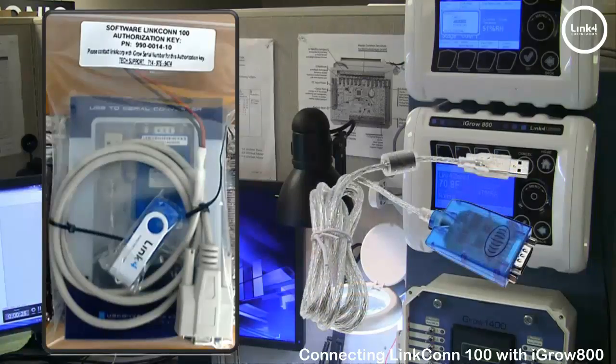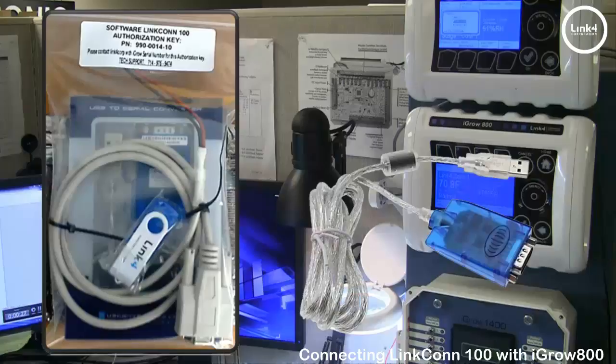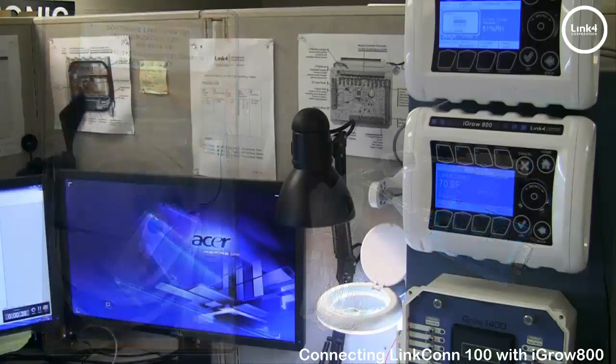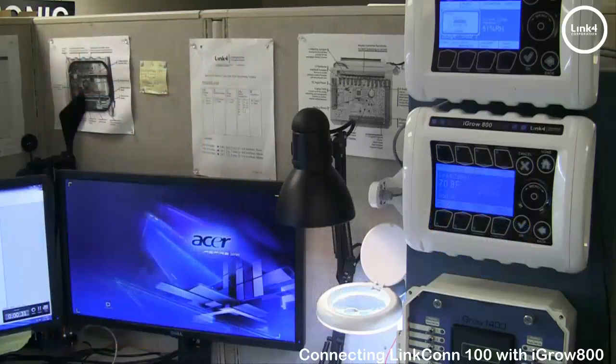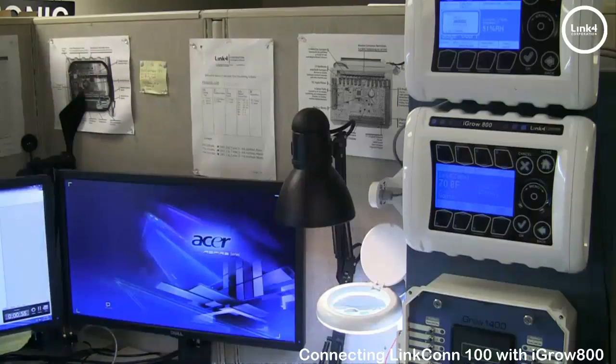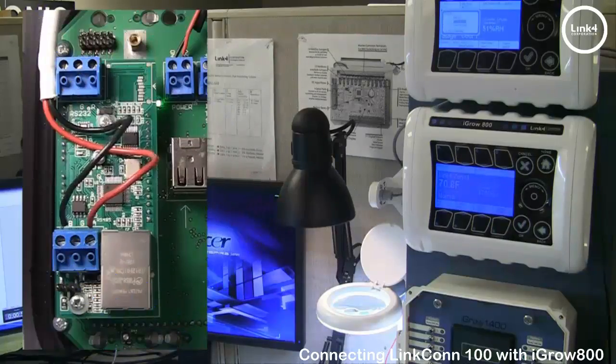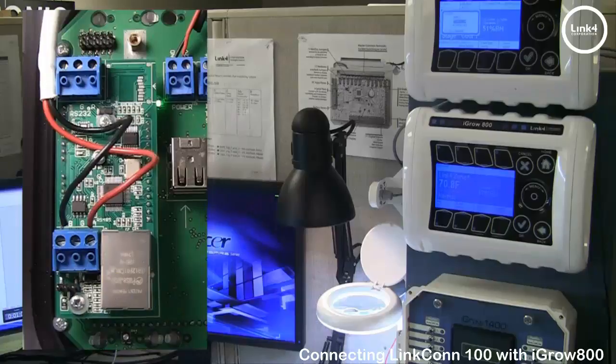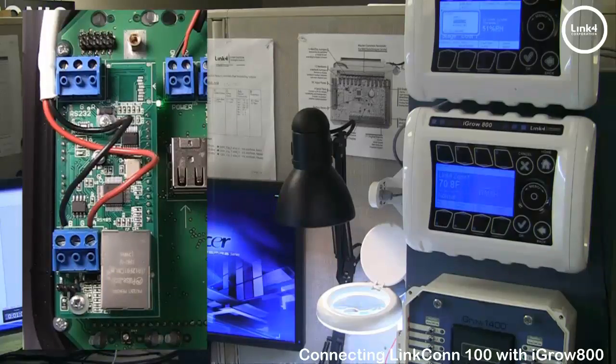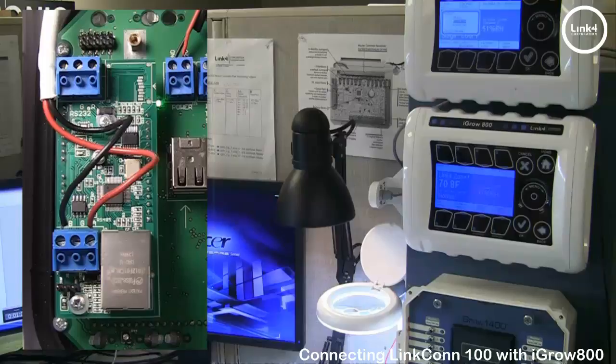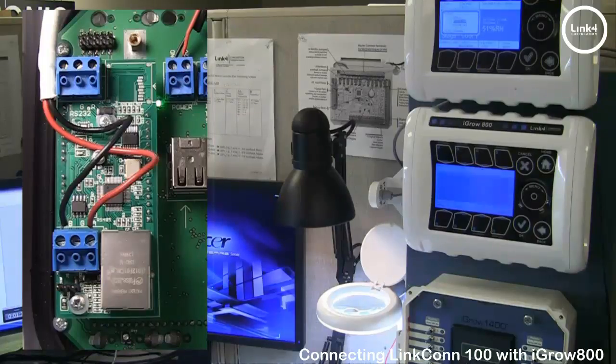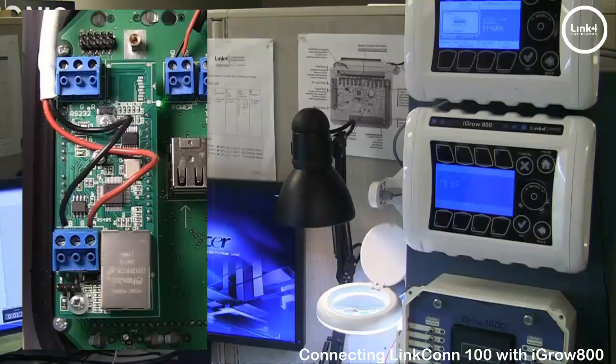To connect your controller to the PC with LinkConn you would do the following: On the communication module from the RS-485 terminal block you want to land your two wires preferably red on A and black on B and then you want to extend your two wire run from the greenhouse to the PC location.